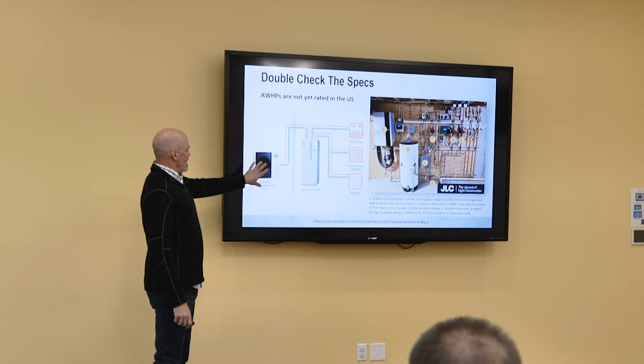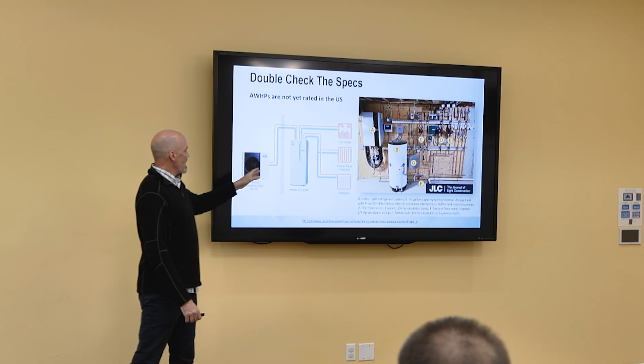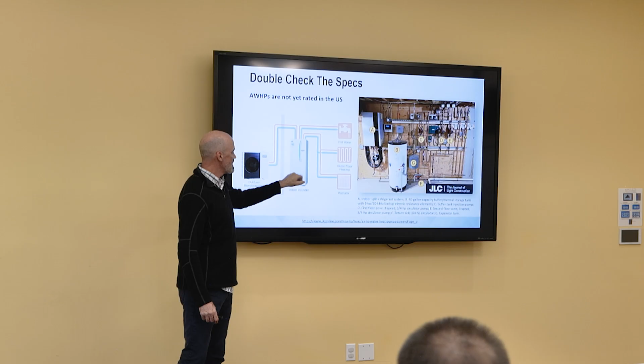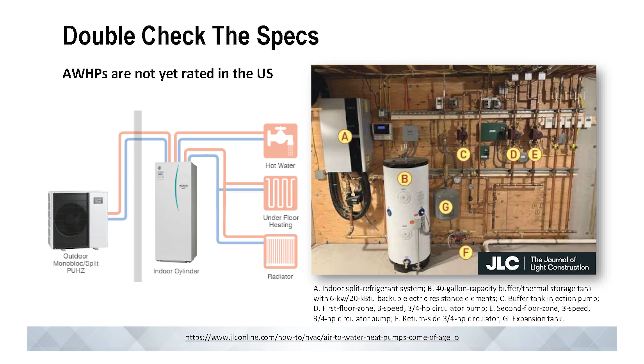This product, Mitsubishi, Daikin, others are bringing product in from Europe, and they're able to do magic things. This is literally a magic box, it does a bunch of stuff: hot water, space heating, cooling, in-floor heat, low temp radiators, convectors. There's all sorts of capabilities around that. You might have to swap out that 150, 180 degree radiator with something more efficient, basically effectively double the area, twice the length or twice as high, more of a European style convector.